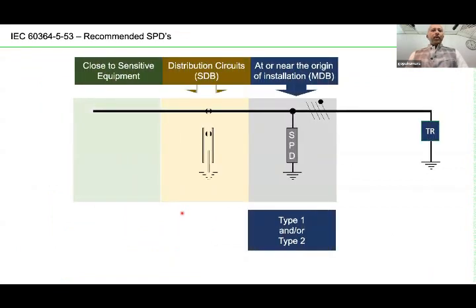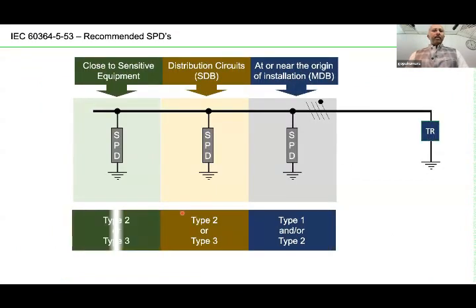From the standard point of view, this is also categorized. For example, you have the transformer at the main distribution board. You can see here 3-phase and the neutral. You have the SPD. This is a type 1 and/or type 2. Sometimes you can use type 1, or you can also use type 2. At the main distribution board, type 2 is also allowed.